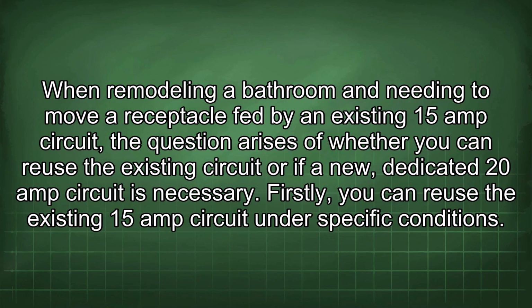When remodeling a bathroom and needing to move a receptacle fed by an existing 15-amp circuit, the question arises of whether you can reuse the existing circuit or if a new, dedicated 20-amp circuit is necessary. Firstly, you can reuse the existing 15-amp circuit under specific conditions.